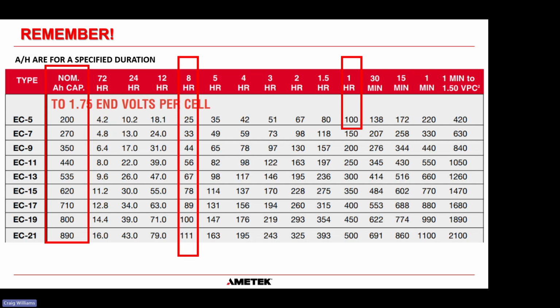But remember I said I would come back to ampere hours? Remember, ampere hours are for a specified duration. So here's a data sheet from ENESYS, and this is for the EC series of batteries. Okay. Now, the first box here says the nominal ampere hour capacity. Okay, so for the EC5, they say that that is a 200 ampere hour battery.